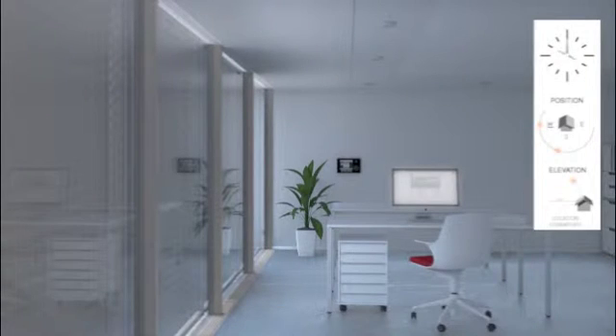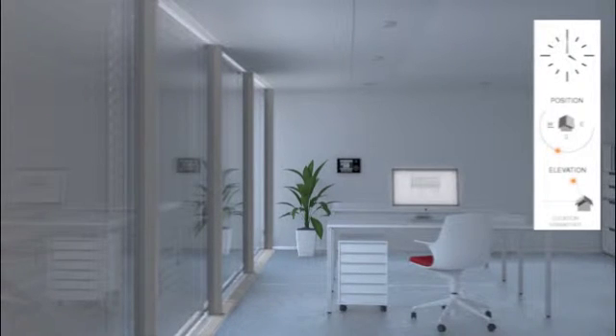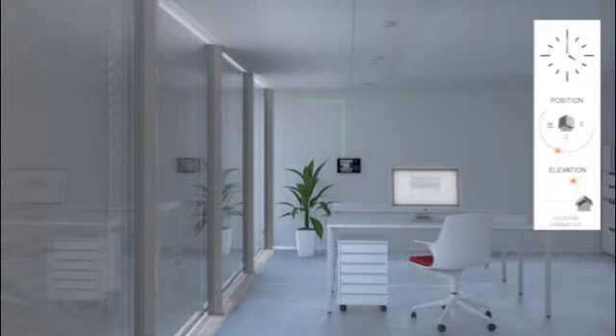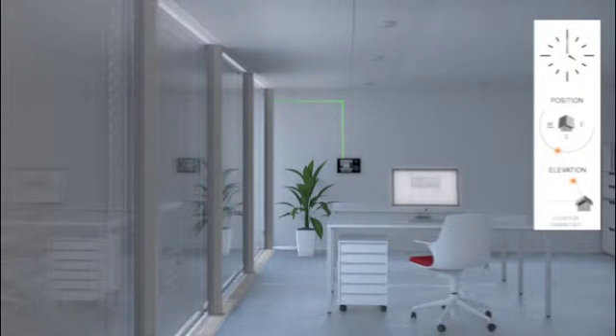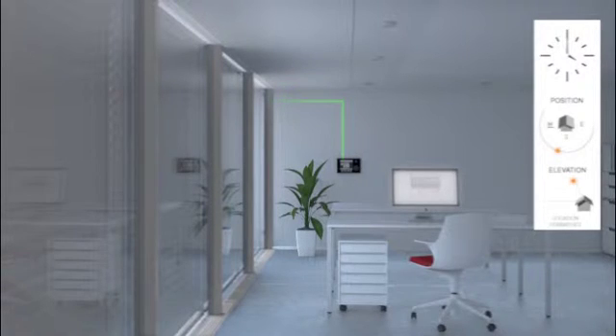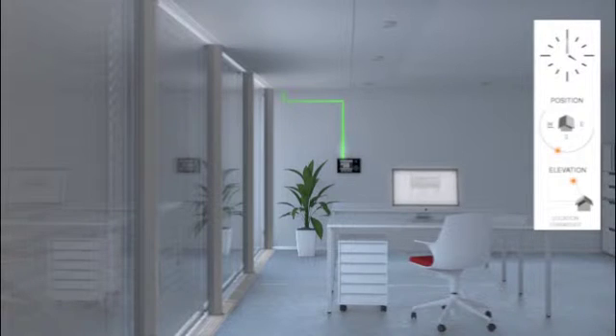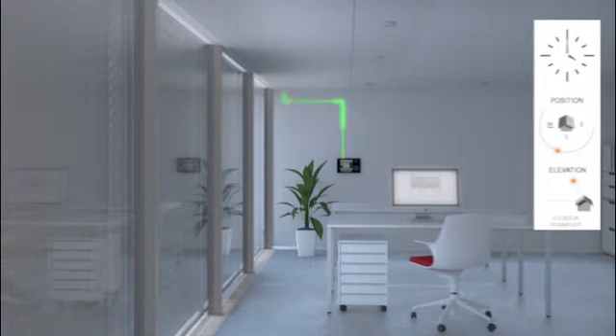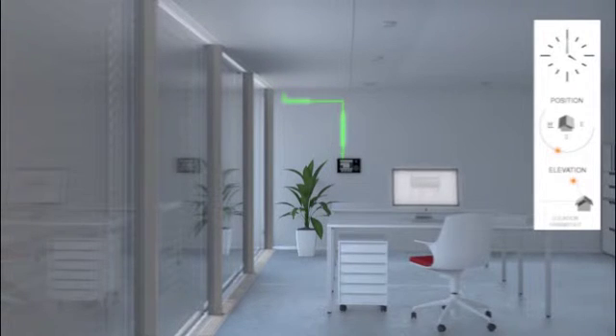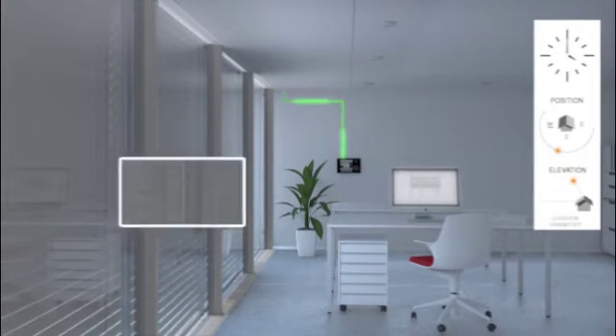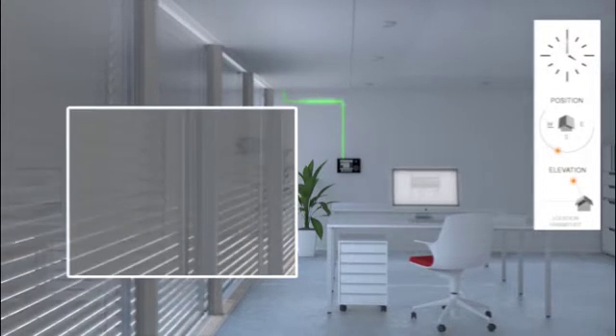Compared to this now the lighting conditions when external Venetian blinds are aligned by the WAREMA Climatronic. The control system records the current lighting conditions, determines the ideal slat position by means of the geographic location of the building as well as the course of the solar radiation during the day and sends the move commands to the motor which sets the ideal inclination angle.